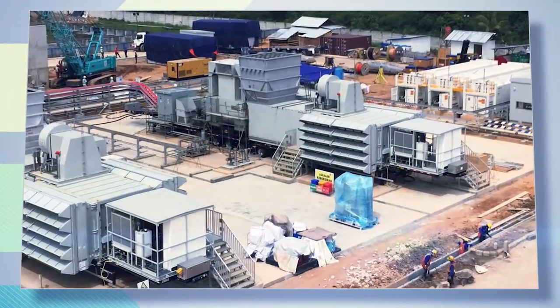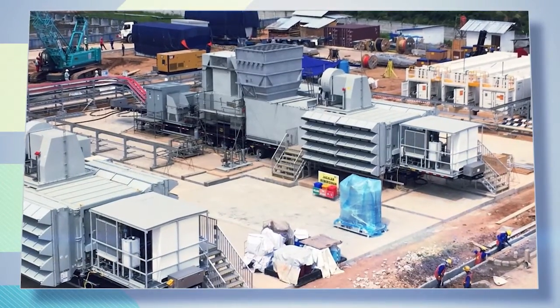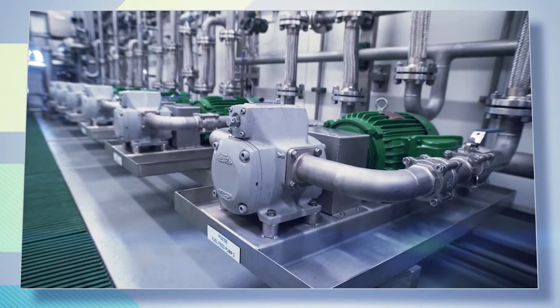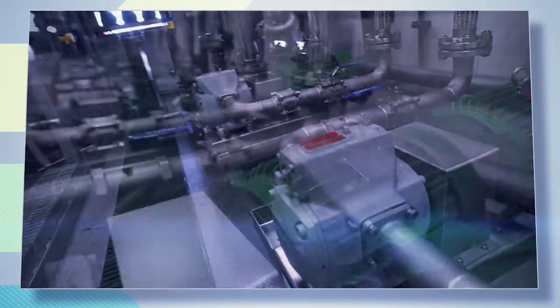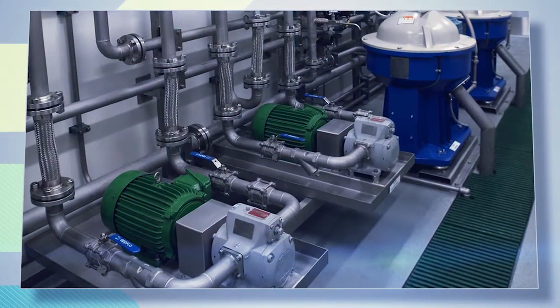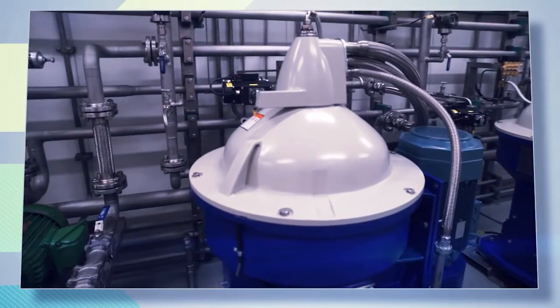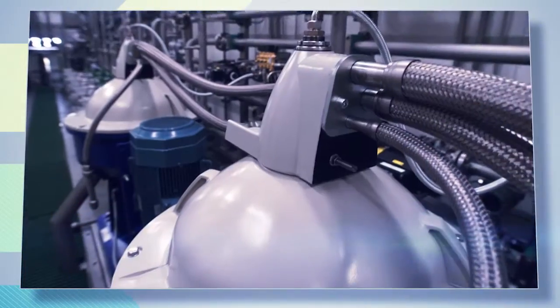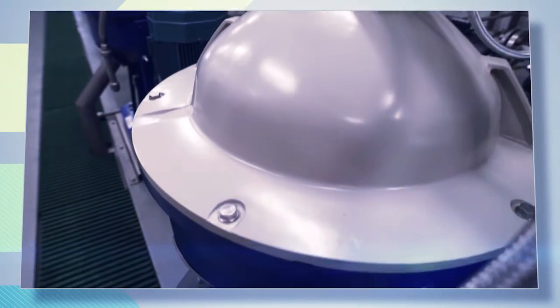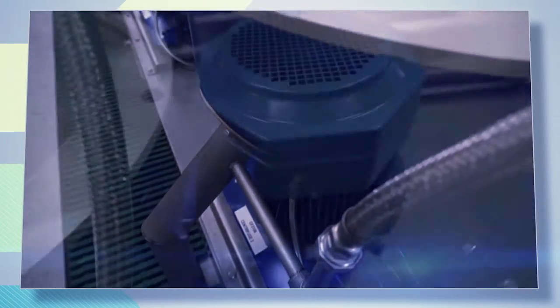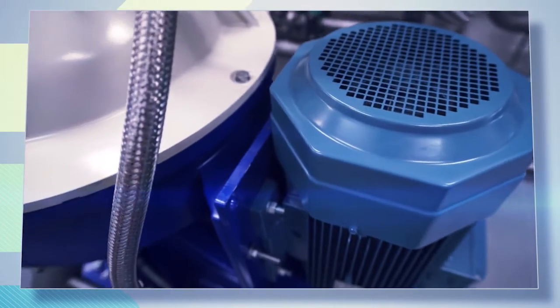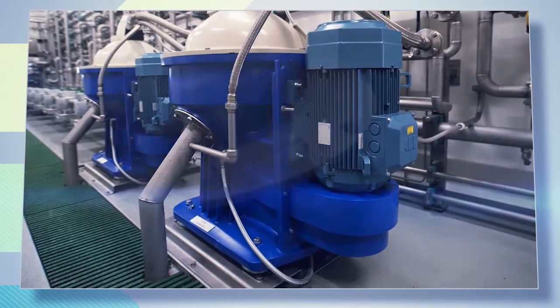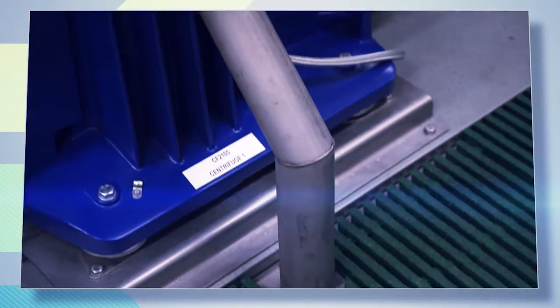There are 12 fuel blocks currently in service in Indonesia. Vane-type positive displacement pumps are employed for all fuel block transfer operations. The pumps are direct coupled to variable speed electric motors. The centrifuges are rotating disc-type separators. They process continuously to produce clean fuel in heavy phases. Variable speed controlled motors drive the bowls via a centrifugal clutch. Bowl operations and discharges are performed using process water.